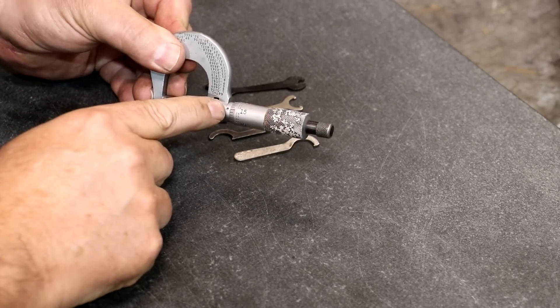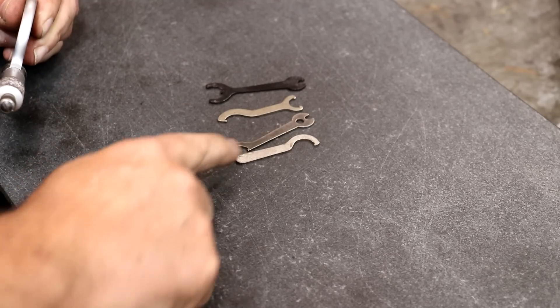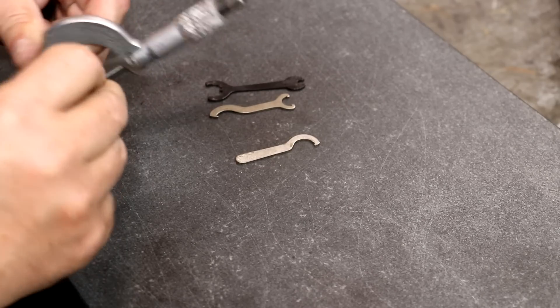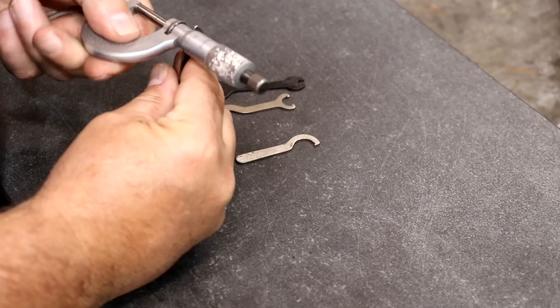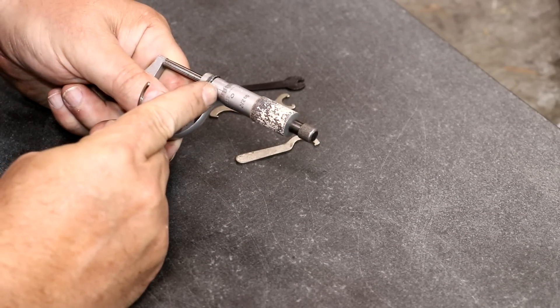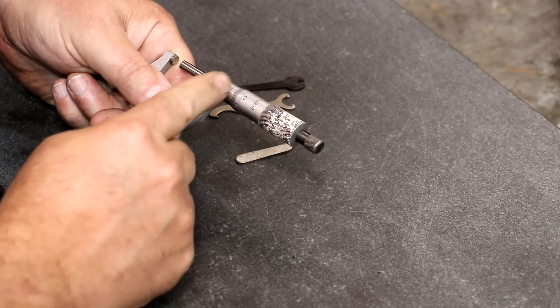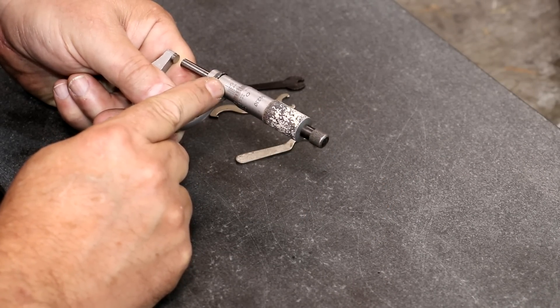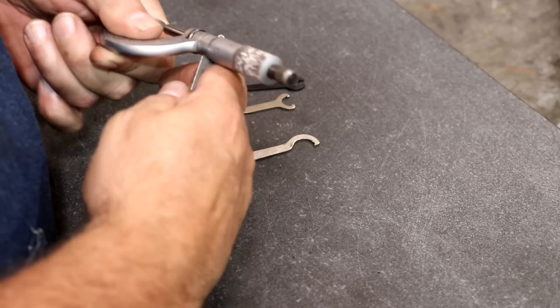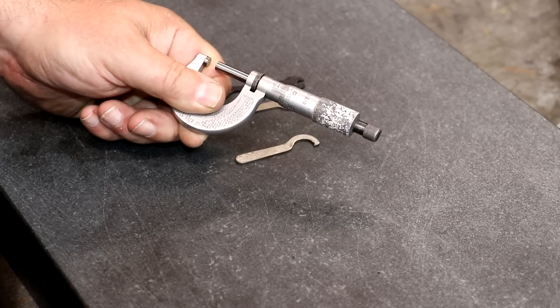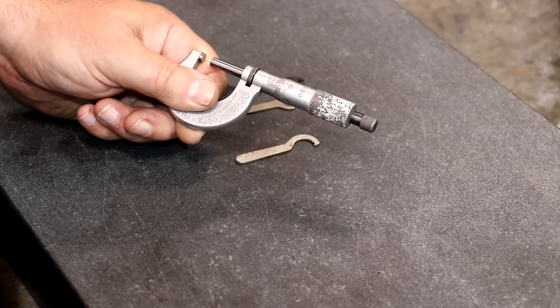If you look on the back of this, there's a little hole right here. And back here, I have some micrometer wrenches. These are some various ones that I've just got over in my toolbox. And I'm just going to use this one right here. But if you look, this little wrench, there's a little pin that fits into that hole. And you can then come over here and use that to turn this barrel, this barrel up underneath here, the one that has all the lines on it. It will turn, it's a tight fit, but it will turn. It's just kind of pressed on there. And you can make little changes in there. So you just basically come in here, put that on there, and you just spin this where it lines up where it should on zero at a particular calibrated interval. So that's how you make your adjustments is just by twisting that barrel.